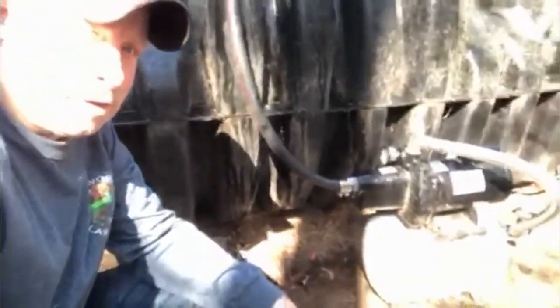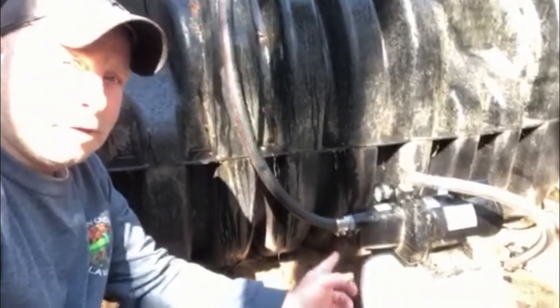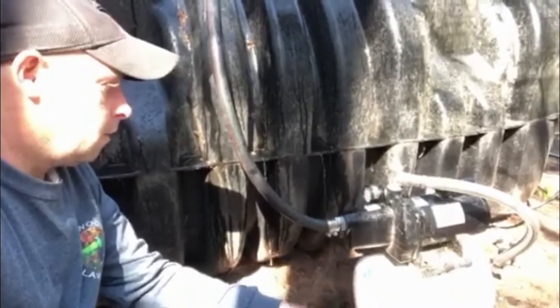Now we're going to plug that jet pump in. We're actually pumping water into the feed line — we don't have to prime the old way. The only thing you need to do is relieve air pressure, and as you can already see, it's almost done. It's pulling water — I can already unplug the first pump. Done, we are up to pressure.